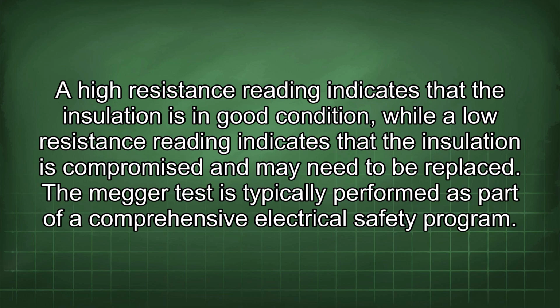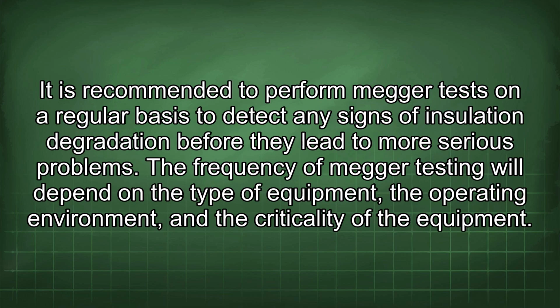The megger test is typically performed as part of a comprehensive electrical safety program. It is recommended to perform megger tests on a regular basis to detect any signs of insulation degradation before they lead to more serious problems. The frequency of megger testing will depend on the type of equipment, the operating environment, and the criticality of the equipment.